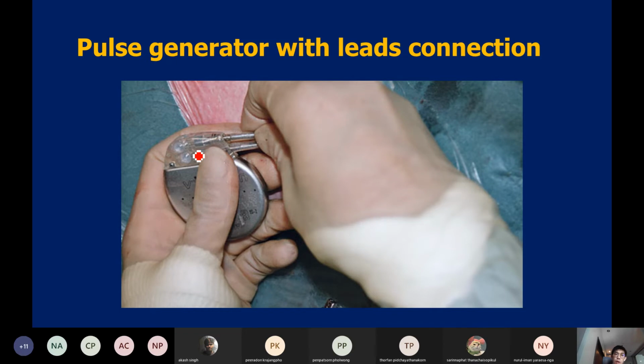Before connecting the generator and the leads, you have to identify that the atrial lead goes into the A channel and the ventricular lead goes into the V channel. This is very important, because if you put the V lead into the A channel and the A lead into the V channel, it would cause a problem with pacing. It would cause a header switch, leading to pacing failure in some patients. If you are implanting the device with the doctors, you have to identify the leads by reading the serial number on the leads, or ask the doctor to read the serial number before you connect it into the channel.